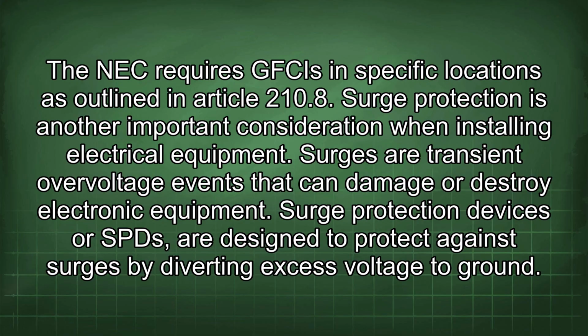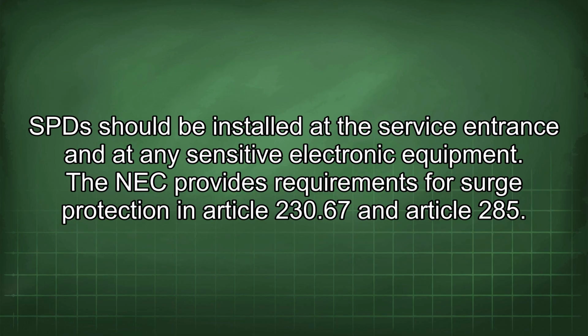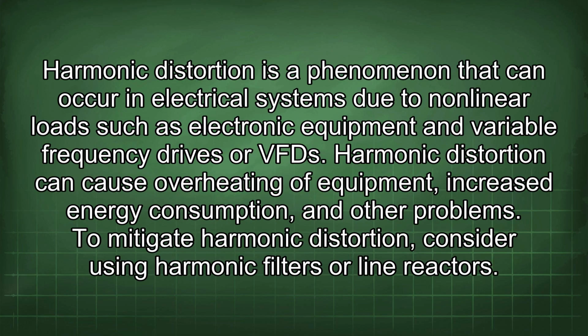Surge protection is another important consideration when installing electrical equipment. Surges are transient overvoltage events that can damage or destroy electronic equipment. Surge protection devices, or SPD, are designed to protect against surges by diverting excess voltage to ground. SPD should be installed at the service entrance and at any sensitive electronic equipment. The NEC provides requirements for surge protection in Article 230.67 and Article 285.